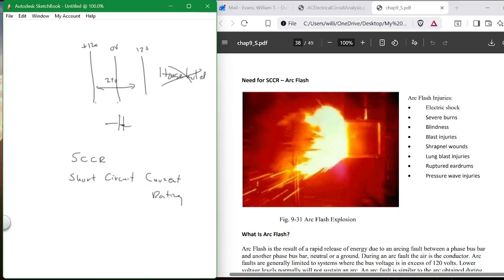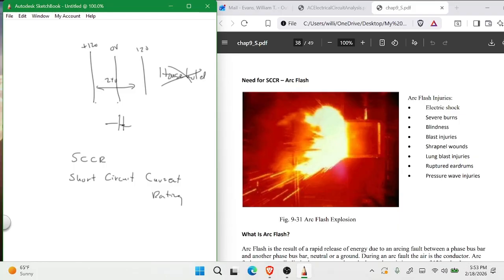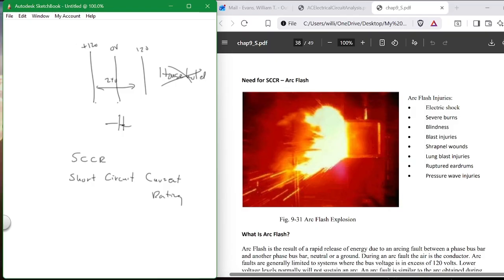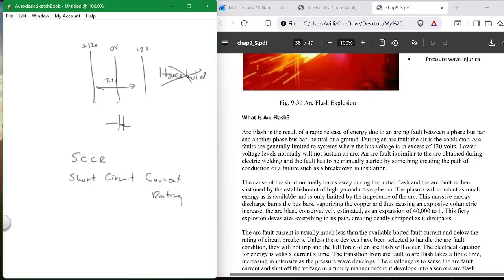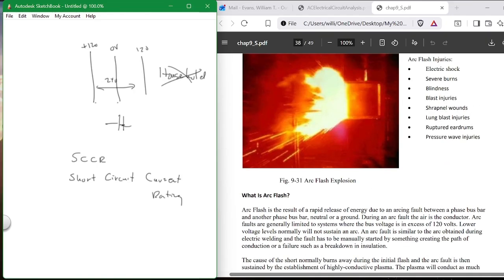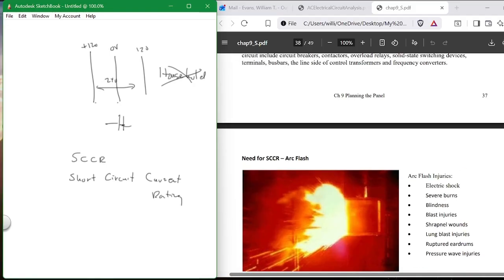I don't want to scare you or make your life miserable, but this is a real possibility, so be careful. The panel should have this rating on it, and you should be trained and certified before you open a panel. Panels at 24 volts or anything under 50 volts don't carry a rating, so you can walk in without worrying. 110 volt panels are level 1, not bad, but once you get to 480 volts with high current ratings, you can end up needing that suit. And yes, they air condition them so you don't overheat.